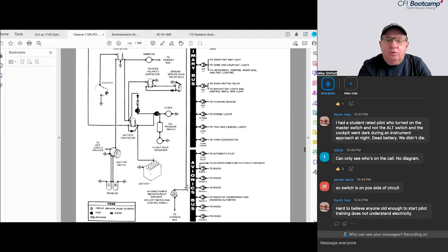Here's the battery, here's the contactor. Currently we can't get anything past this point because the contactor is not closed. Turn the master switch on, which is up here, and that will energize the coil, which will cause it to close. Then we'll be able to get current to flow from here through the contactor, up to the starter contactor, which is not closed yet, through the ammeter to the main bus. And now we're at the main bus.